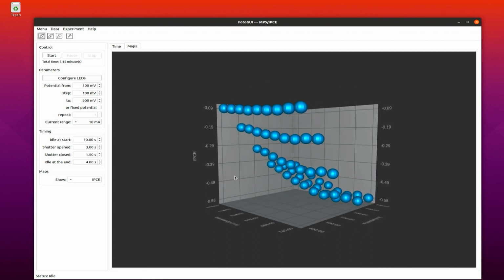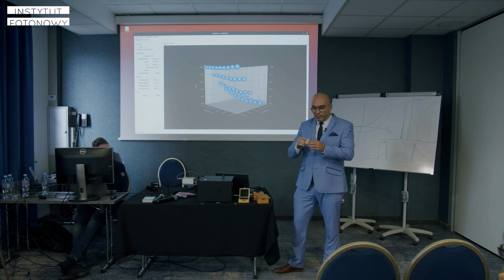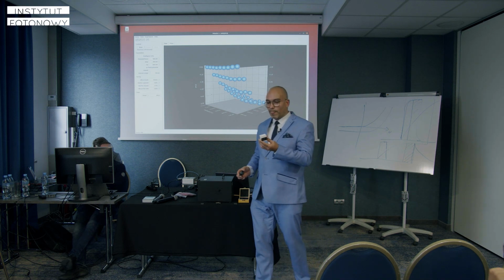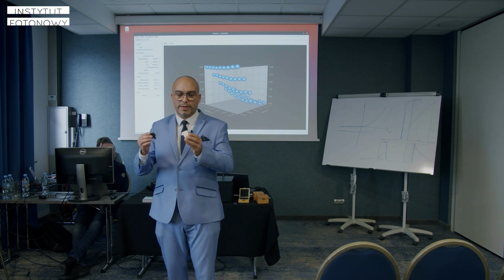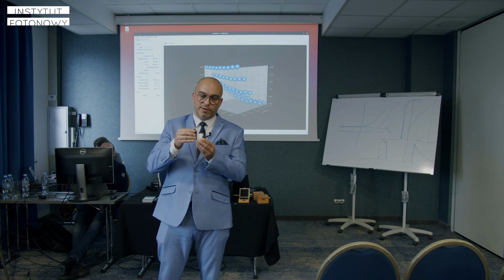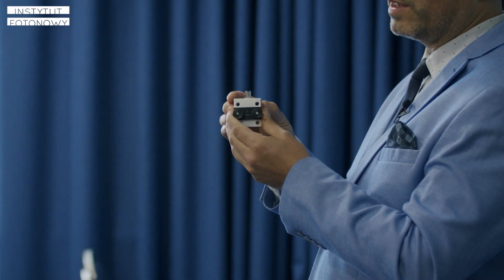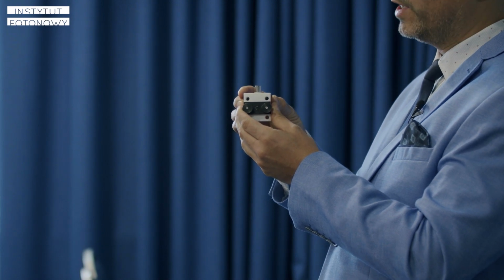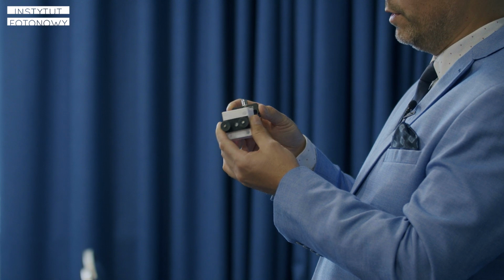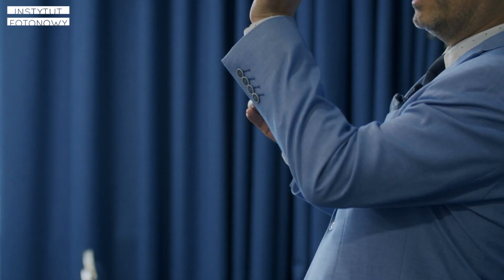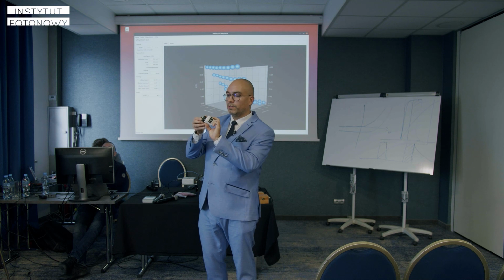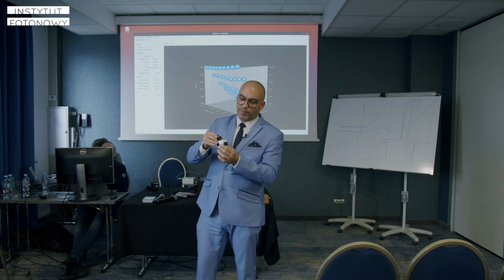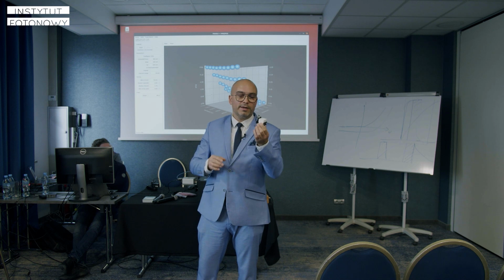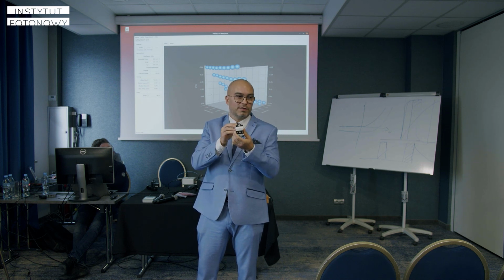And for this purpose, this is possible because we have done the calibration before. So if you use our cuvette, it is designed this way: if we want to know how much light is absorbed in the sample, we measure, here is a window, this way, sorry. We place the calibration head here. This is fit to our cuvette.